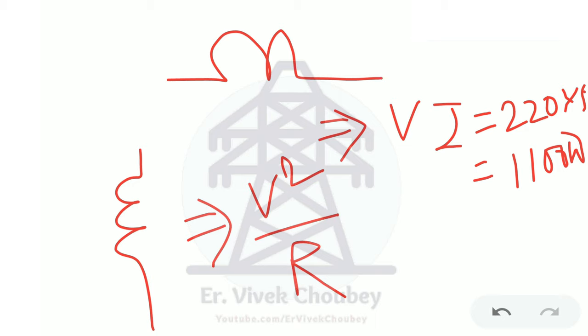Now what we are seeing here is that the power loss across the current coil in an actual loading at the full rating is 1100 watt, which is alarming, because this amount of power is just being wasted as we are not using it across any real load, rather we are using this power for testing purposes.